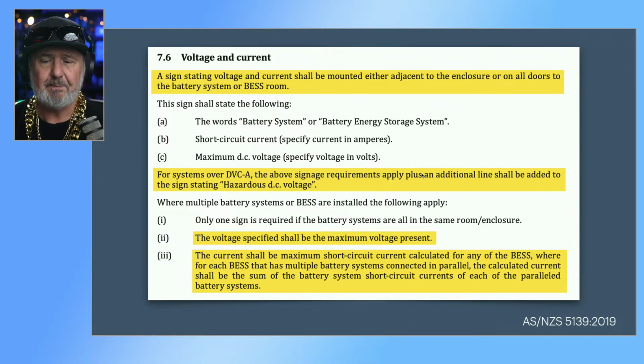When this standard was first published, by the way, there was a lot of confusion, because a lot of manufacturers just assumed that if there was internal overcurrent protection on a battery system, like a circuit breaker or a fuse, that would be the short circuit fault current, but it's not. A short circuit fault current is the peak before the tripping occurs, because that's a point where an arc can be struck, even though it'll be extinguished as soon as the trip occurs. In the case of, say, LG Chem's Resu 10 units, 10 kilowatt hour units, which are nominally a 56 volt nickel manganese cobalt, NMC, battery, the breaker is 160 amps, but the fault current, according to the manufacturer, is 2,250 amps. So yeah, it's way more than just the overcurrent protection device itself.